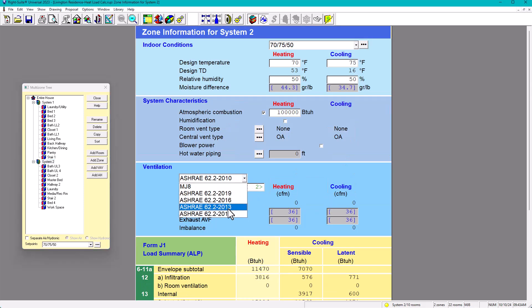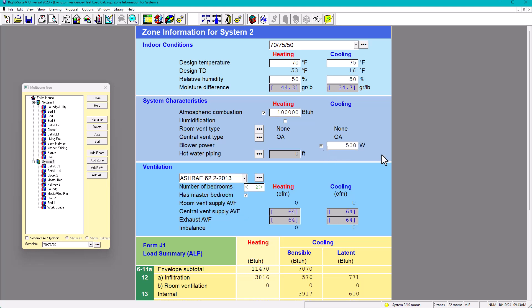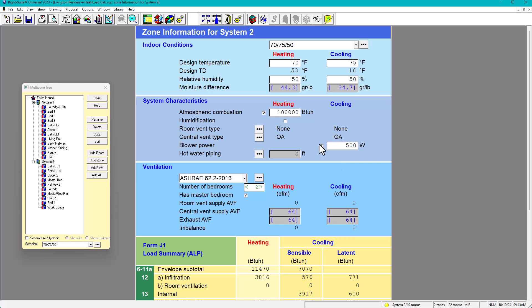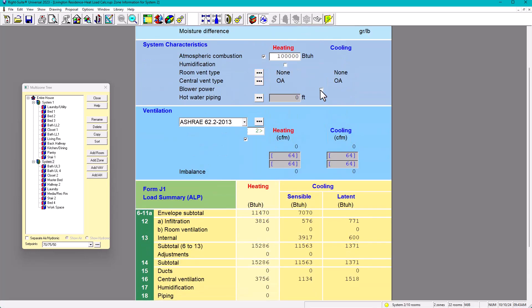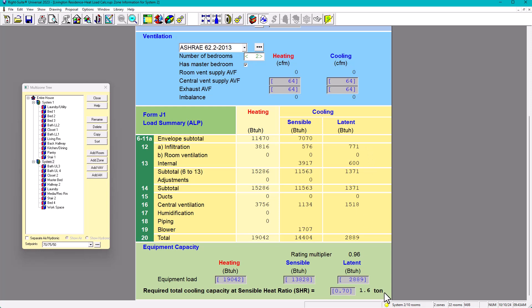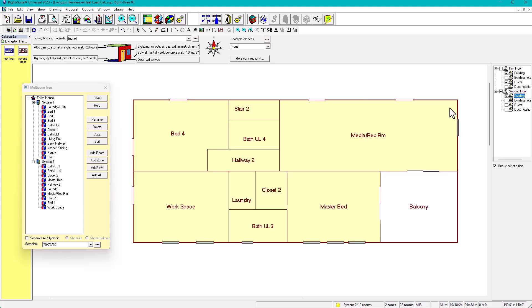For System 2, using ASHRAE 62.2 2013, without blower power it's about 1.5 tons and with blower power 1.6 tons. I would put a 2-ton unit, especially if the unit is located in the attic, because unfortunately the attic causes significant energy loss.